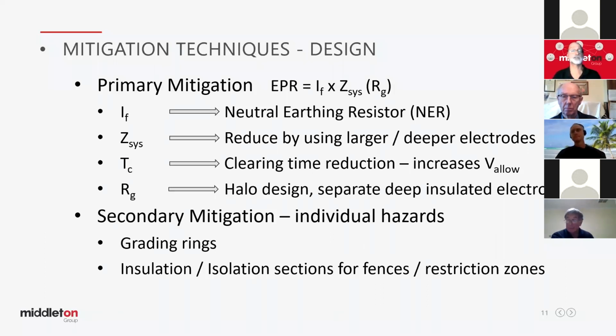So they've got to be managed, and utilities will accept these designs. However, think about it, quite often the situation where we use these is in subdivisions. So you get a new subdivision out the back of Sydney or back of Melbourne, in rural land, and that subdivision doesn't have the benefit of an MEN to bond to, to help bond through your overhead earth wires, as you talked about earlier, to join and bring the system impedance down and reduce the EPR.